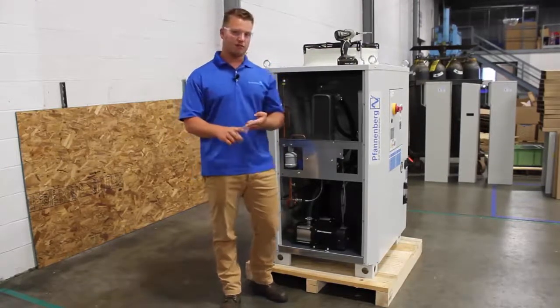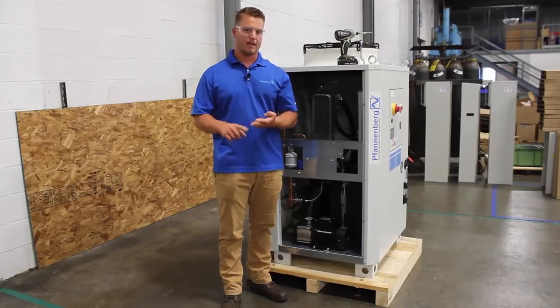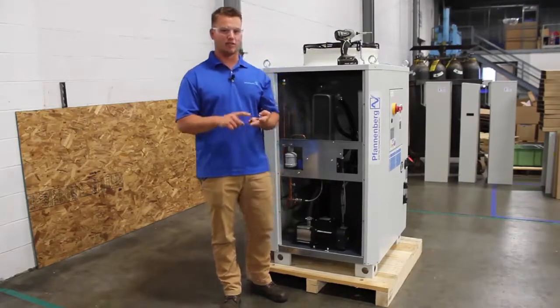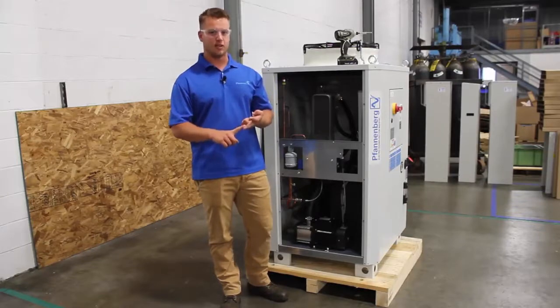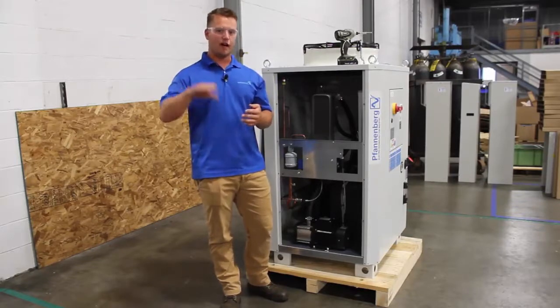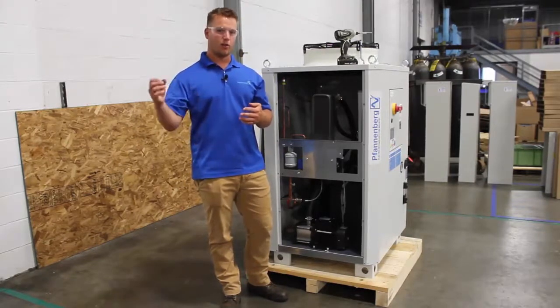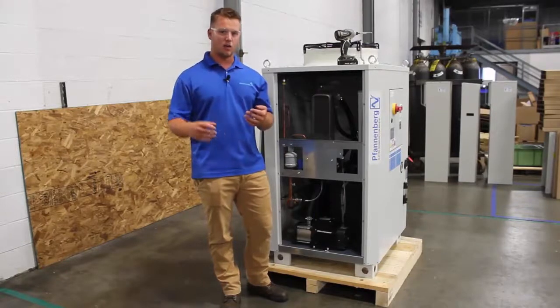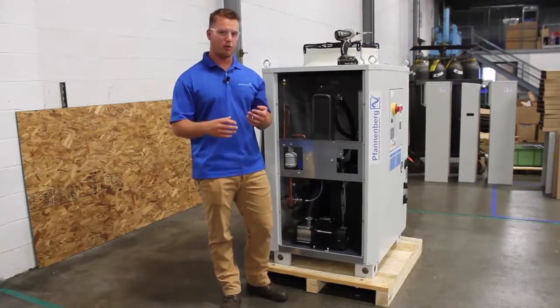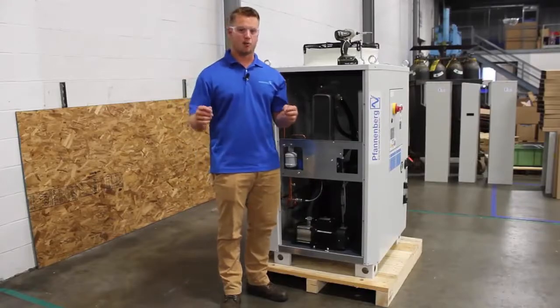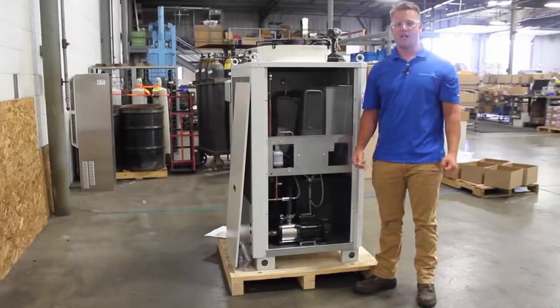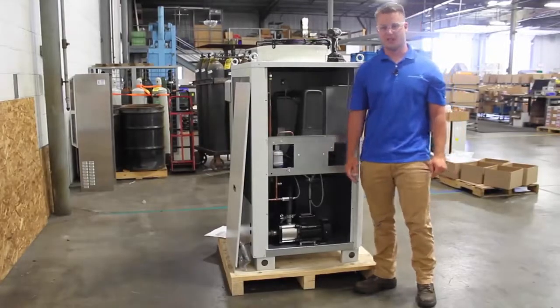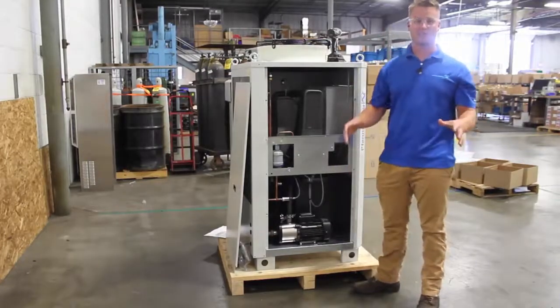The second feature we have to protect the pump is an electronic tank level sensor. The tank level sensor is going to measure the level of the tank, so when the pump's pulling fluid out of the tank, we're not pulling dry air into the pump. Again, we never want the pump to run dry. All right, since we're inside the chiller, we're going to stay inside the chiller. Now I want to talk about the refrigeration system.